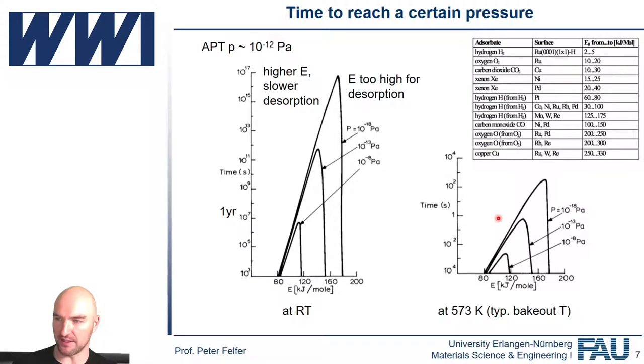The main reason for that is that very often we have thermally well insulated parts of our system and the heat needs to go everywhere. That's why we can't just heat it up for a couple of seconds and then cool it down again. We rather need to keep it at temperature for a little while, typically 24 to 48 hours. Anything longer we only do on new systems where, for example, water vapor comes out of polymers, because polymers can take up a certain percentage of their weight in water vapor, and that just comes out slowly. But once that's done, every time you open the system, you might take 24 to 48 hours of bakeout.